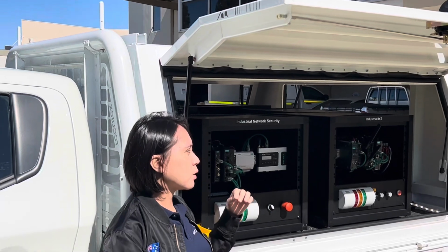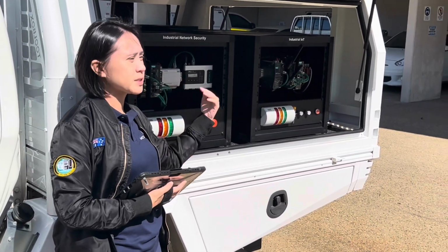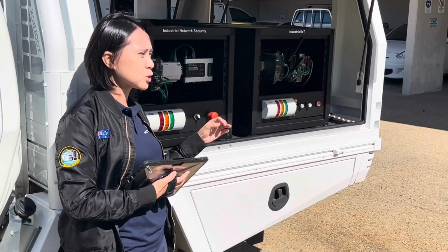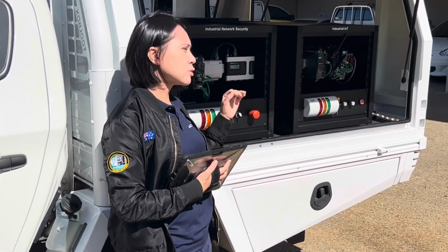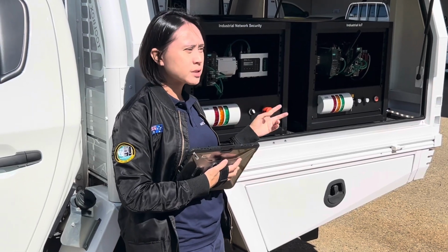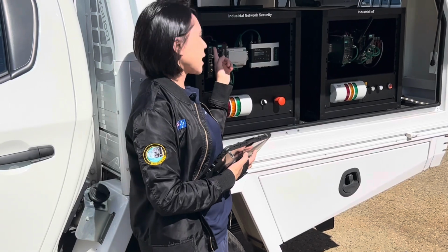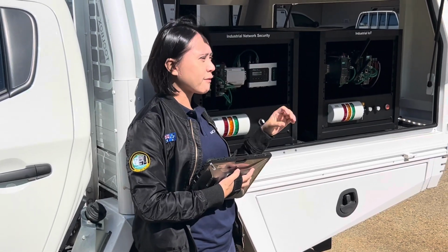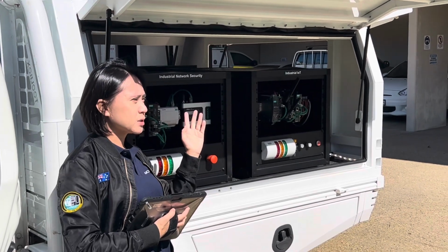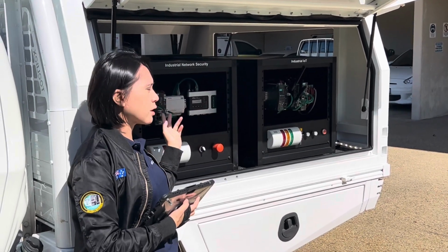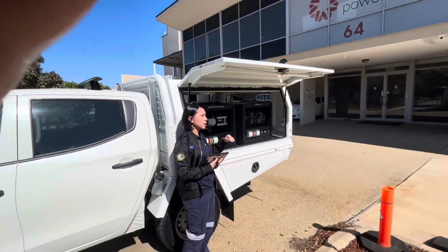Yeah. So if you use Modbus, you know that when you try to pull some address or some information, you need to define what the function code is, what the address is. And some function codes can read and write, some function codes can just read. So this can even look into the detail of the traffic. If it's a write, the function code will be blocked.